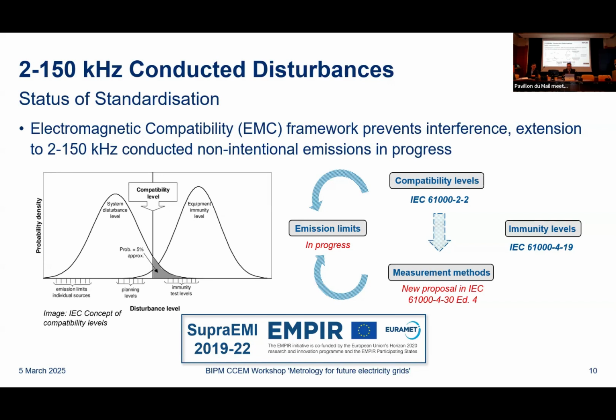So we've got compatibility levels, which have been defined up to 150 kilohertz. We've got immunity levels and emission limits. We have some, but they're only really for specific appliances, for example lighting and induction cookers, but especially for things like EV chargers, which are very big emitters, and we're going to hear more about that today. It's getting there, but it's still in progress. And for the grid measurement method, which I'm going to talk more about, there's a new proposal on the table in the 61000-4-30 standard. That's been published for comments last year, so the next edition should be out in the next 1 or 2 years.